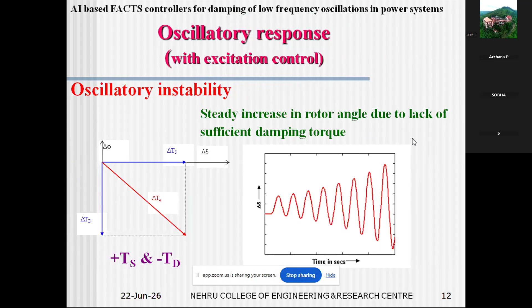Now, if you have enough damping torque, there are different methods by which the damping torque can be improved. In that particular case, your synchronizing torque is positive because it is working with an AVR, and damping torque is positive because you are using various techniques to improve the inherent damping of the system, by examining the various modes of oscillations and adding some compensators to the system. The system will have sufficient synchronizing torque and sufficient damping torque, and then your system becomes stable, even if it is subjected to small deviations in load, small deviations in excitation voltage, or small deviations in generator frequency. You can then say that you have a stable system.